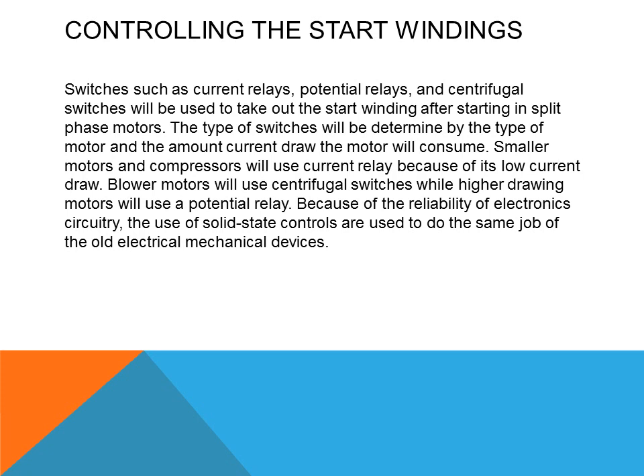Another variation operates similarly to a regular split phase motor but without a centrifugal switch, and is used in applications like air handlers, ceiling fans, and other fan-moving devices where the load can vary. Switches such as current relays, potential relays, and centrifugal switches are used to take out the start windings after starting a split phase motor. The start windings cannot stay in the circuit — if they did, it would damage the motor. Another type of switch is a solid-state relay, which does the same job as electromechanical devices but has no moving parts, making it more reliable and less prone to wear out.